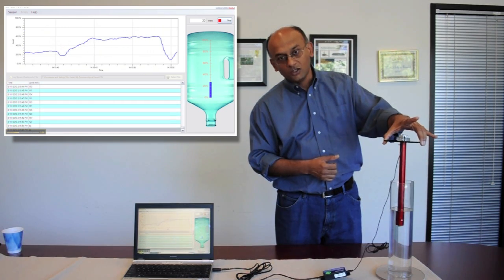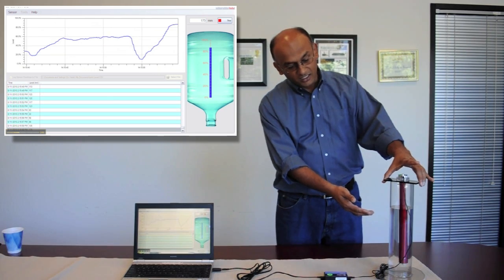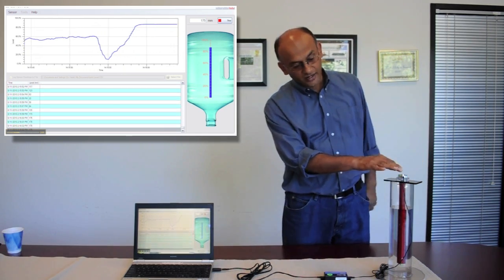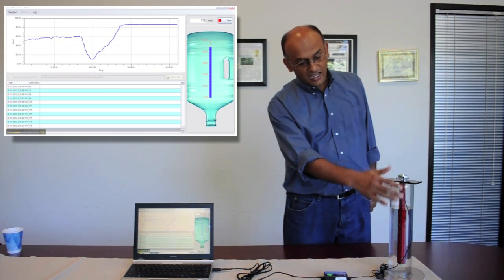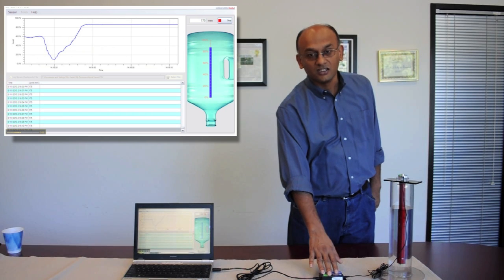So, as I dip the tube in, the capacitance increases, and the increase in capacitance is measured by the electronics right on top of the sensor, and out comes a frequency output that goes into this interface device here.